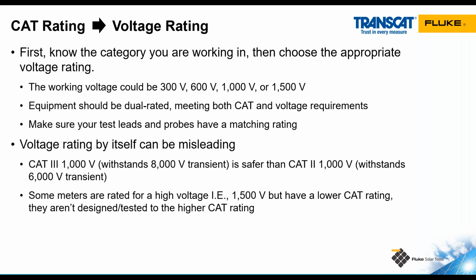Now, one thing that we run into in the test and measurement industry that I like to point out is that not all test tools that are designed to test up to a certain voltage are actually rated to that voltage. For example, you may see a test tool that is rated to test 1500 volts or even 2000 volts, but when you look at the rating, it's actually category 3 1000 volt rated or even 600 volt rated. And so it's not really designed to withstand those transient voltage spikes for that voltage that it's actually testing.